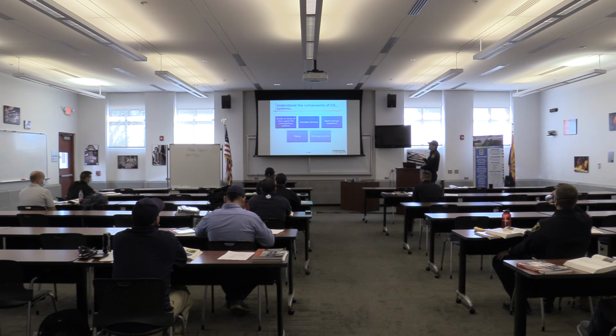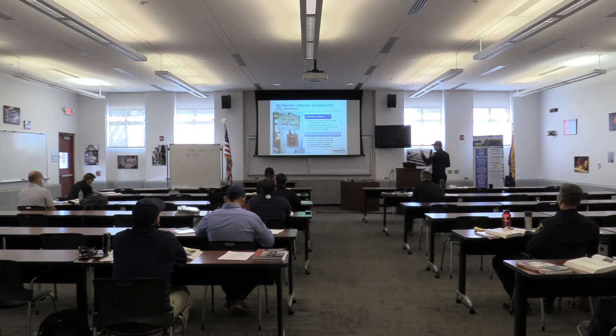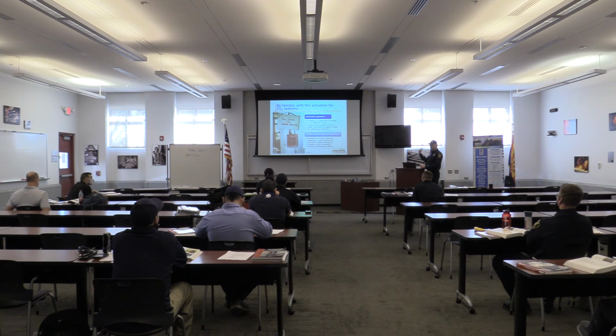You have to have an activation system. The thing with the CO2 systems, though, and what this is telling you is CO2 systems have to be designed so that if there's a fire and the system's going to activate, you need to have an audible alarm prior to the activation of the system and enough time for employees to get out of the room or the building. Typically, the limited area where the activation is going to occur, employees have to be trained on the system as well, or at least understand how the systems work and know how to get out, when to get out.